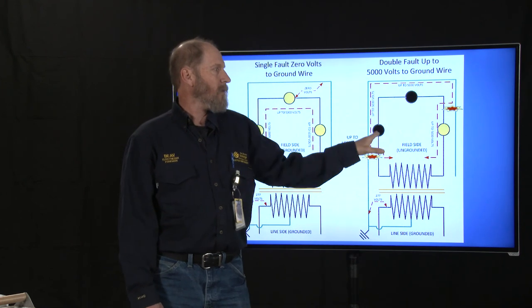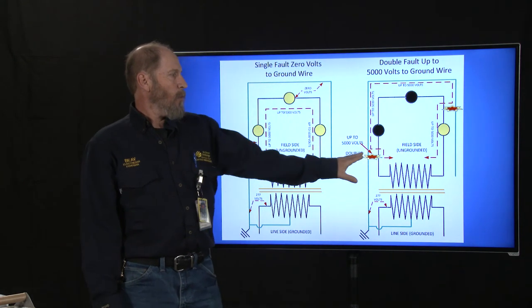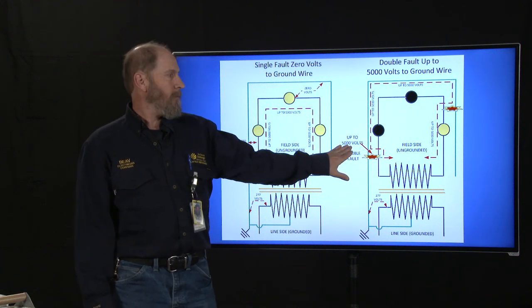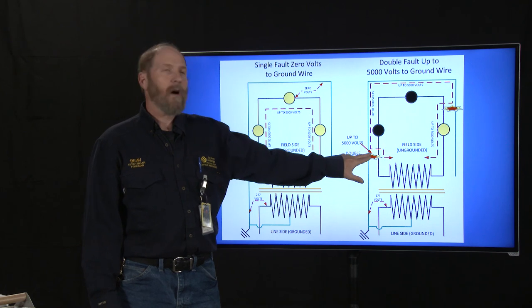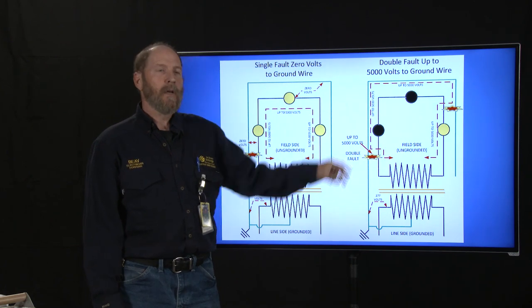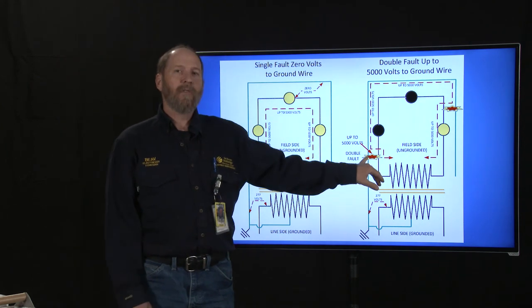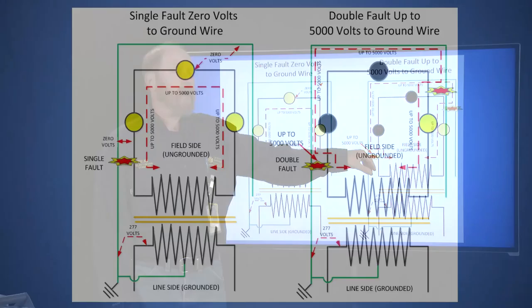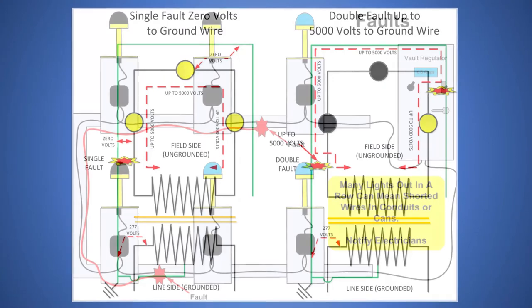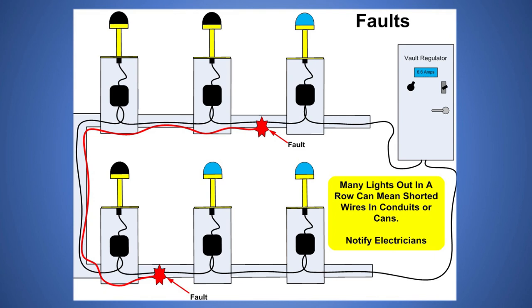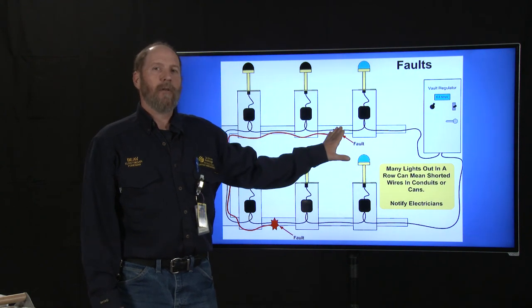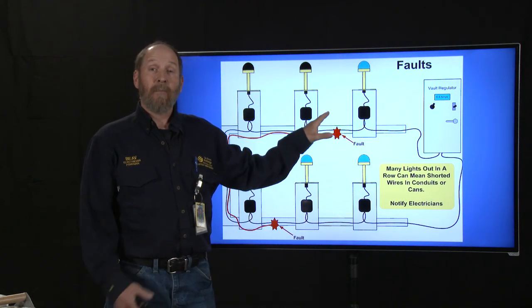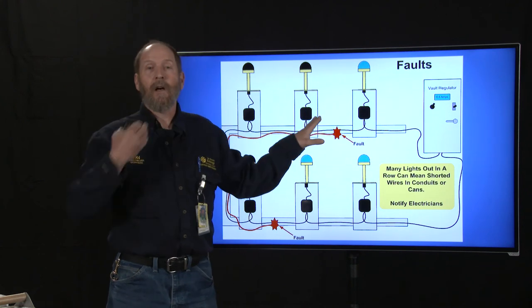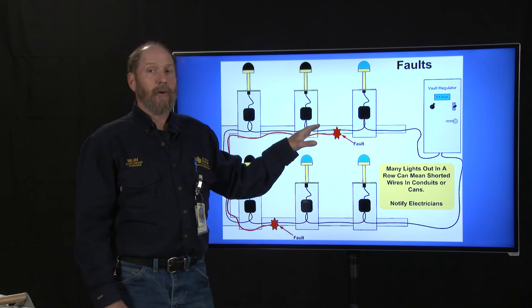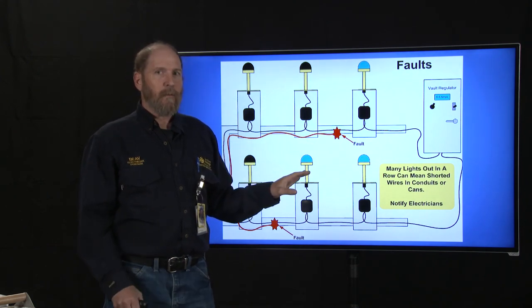What you'll tend to see are lights out in that situation. But in this situation, you have up to 5,000 volts potential to jump across out of that wire onto that ground. So here we have 0 volts. All of a sudden, because we have two faults, we have up to 5,000 volts potential. I've heard it said constant current is a safer type of electrical system because it's not seeking ground. So you could walk over and touch a fault, touch a bare wire, and because it's not seeking ground, it's not going to try to come to ground through you. And so it's safer. Well, actually, that's a true statement.